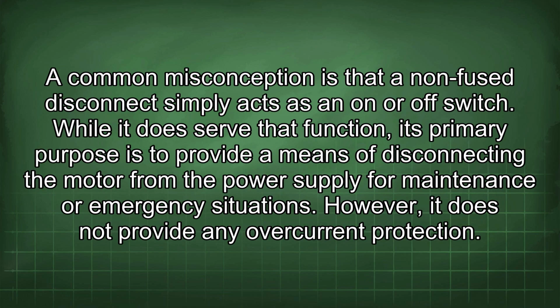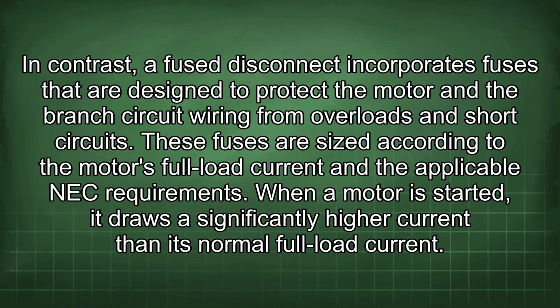A common misconception is that a non-fused disconnect simply acts as an on or off switch. While it does serve that function, its primary purpose is to provide a means of disconnecting the motor from the power supply for maintenance or emergency situations. However, it does not provide any overcurrent protection. In contrast, a fused disconnect incorporates fuses that are designed to protect the motor and the branch circuit wiring from overloads and short circuits. These fuses are sized according to the motor's full load current and the applicable NEC requirements.